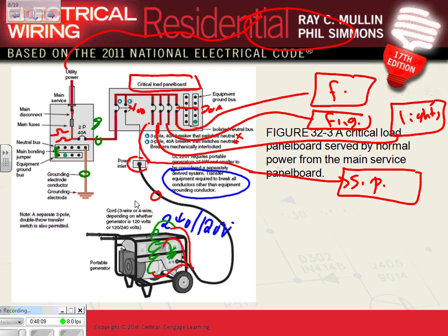Actually, I want to bring to your attention, where's the grounding electrode conductor for this generator? Always, where's the grounding electrode conductor? If it's a separately derived system, I have to go ground a rod and tie it. But this is portable. If it's portable, they allow you guys to bond the neutral, because that neutral here has to be bonded. Look how they bond it. I want you guys to follow with this inside this cable. Can you guys follow that one inside this cable?